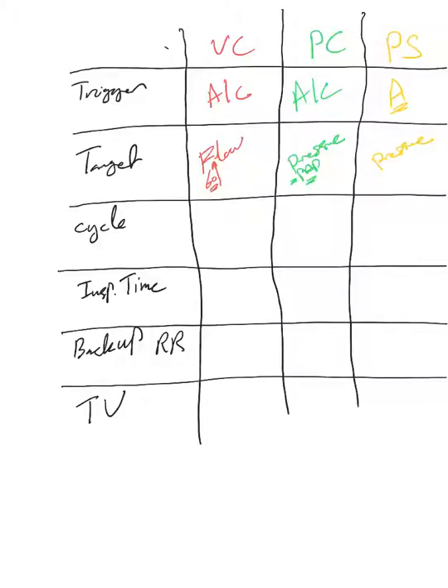For cycle, here is tidal volume. Once the tidal volume is delivered, the breath will terminate. Cycle here is time - we provide how long the inspiration will go. And cycle here is flow - we provide the threshold for the flow, the sensitivity of the flow, at which the breath has to be terminated.